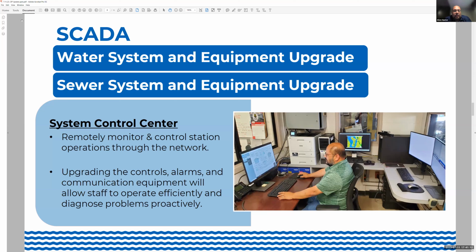The reason for these upgrades is they're meant for us to remotely monitor and control the station operations through the network. I don't know if you're all familiar with the acronym SCADA - it's supervisory control and data acquisition. So it allows us to not only get information from the stations, but also operate the station, turn pumps off, adjust well levels, and so forth.